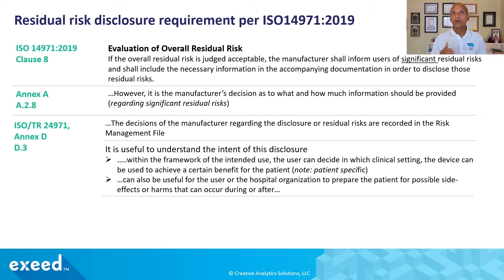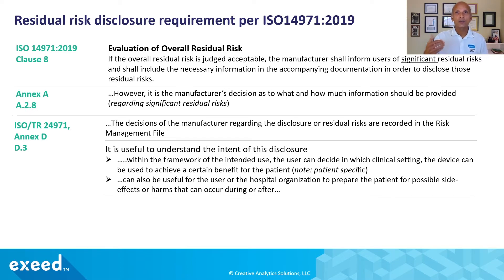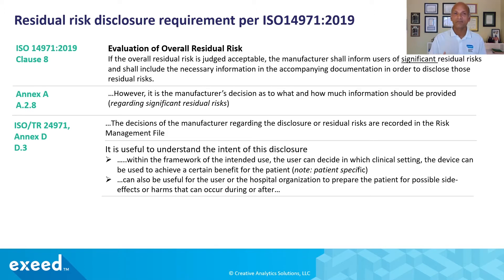What is the intent behind this disclosure requirement? In Annex D of ISO TR 24971, they tell you that within the framework of the intended use, the user can decide in which clinical setting the device can be used to achieve a certain benefit for the patient — it could be patient-specific. You want the disclosure to help the decision be made for a specific patient in a specific clinical setting. It can also be useful for the user or hospital organization to prepare the patient for possible side effects or harms that can occur during or after.